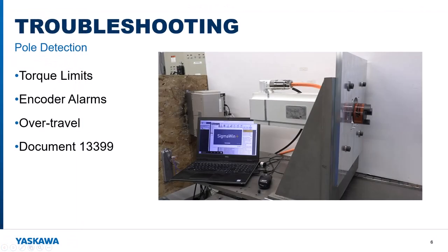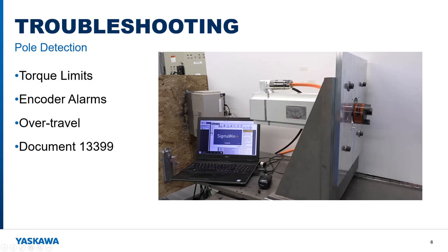Now to wrap it up. It is possible that polarity detection fails. If that happens, check for conditions that could prevent the motor from moving, such as torque limits, encoder alarms, or over travel condition. For a full list of troubleshooting solutions, please see document 13399 at our website yaskawa.com.